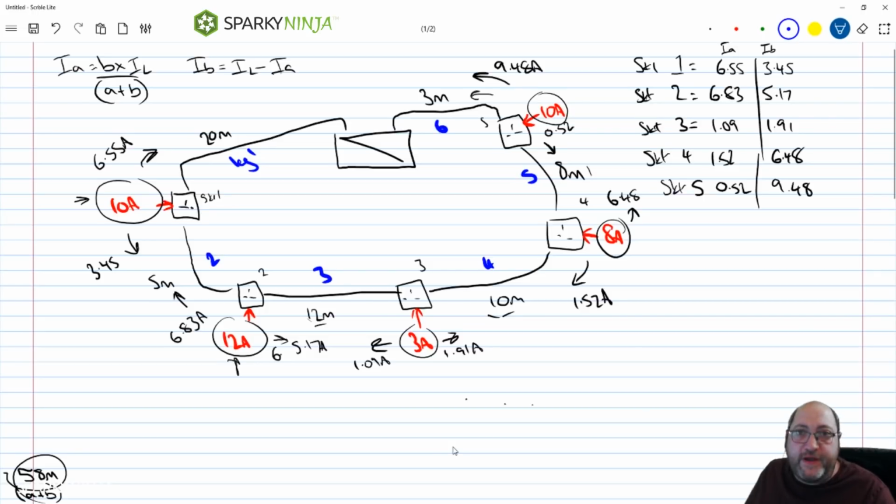Remember, the whole point of this was to ensure that the leg for sustained periods of time will not be more than 20 amps. So we need to hopefully get less than or equal to 20 on each of these legs. And if we get over 20, we've got to assume whether or not the load can be a load of long duration. But let's figure out if any of these loads are going to go over 20.